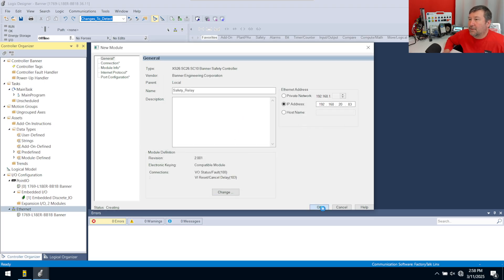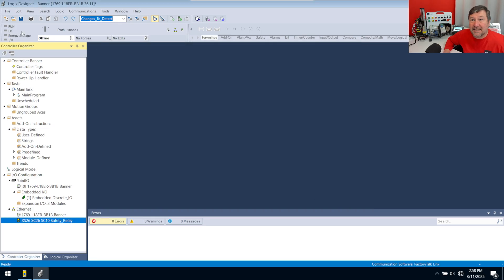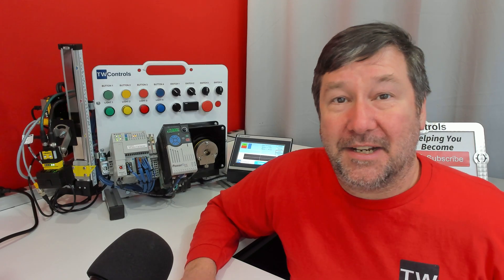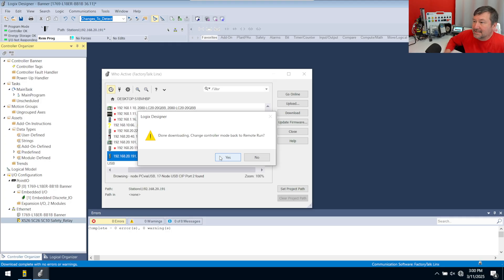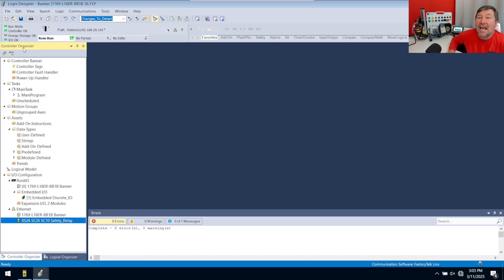Click OK and let's go ahead and download this program and just make sure it works. If you need help downloading your program or with pass-through, there's a link in the description to a course that will walk you through all the basics. Hit Subscribe while you're at it — we put out at least one video a week. Then click Yes to put it back in Run mode. We're looking for a solid I/O light — that's the big thing. If you don't have a solid I/O light, you'll probably see a small yellow triangle.